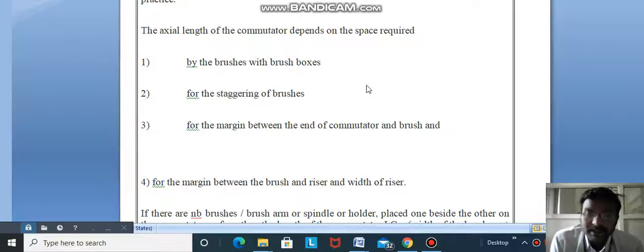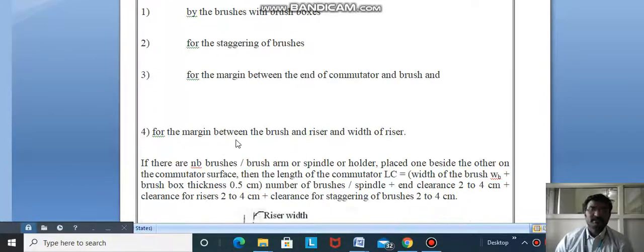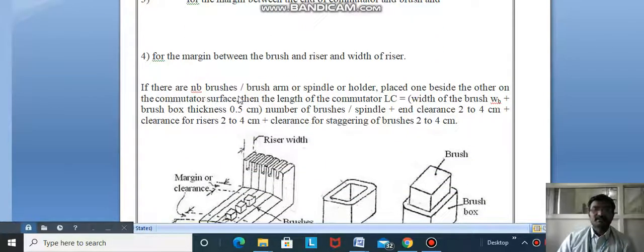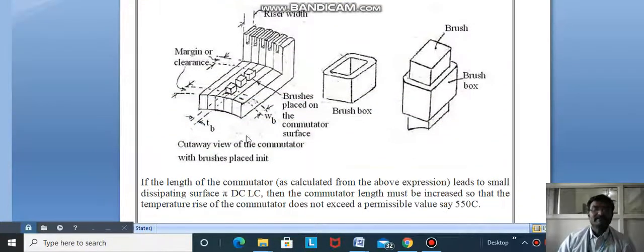The axial length of commutator depends on the space required by the brushes with brush boxes, for staggering of brushes, for margin between the end of commutator and brush, and for the risers. The length of commutator Lc equals width of brush Wb plus brush box thickness 0.5 cm times number of brushes per spindle, plus end clearance 2-4 cm, plus clearance for risers 2-4 cm, plus clearance for staggering brushes 2-4 cm.